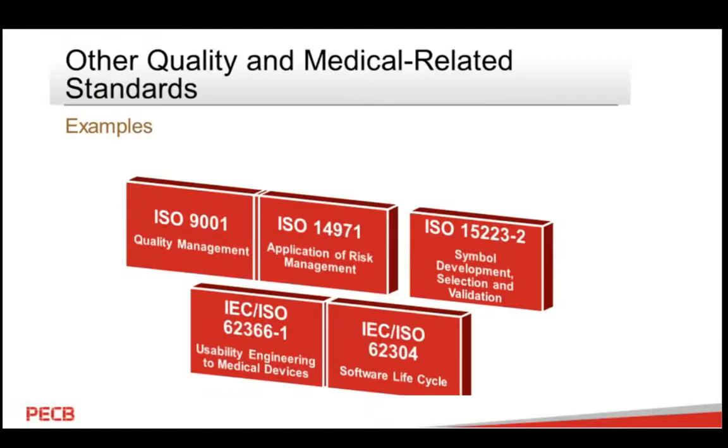Now, this specifies a process for a manufacturer to analyze, specify, verify, and validate the usability related to the safety of a medical device. So if you are building your medical devices, how feasible is it to use? Is it usable, or is it working properly in the environment? For auditing these, you have this one.